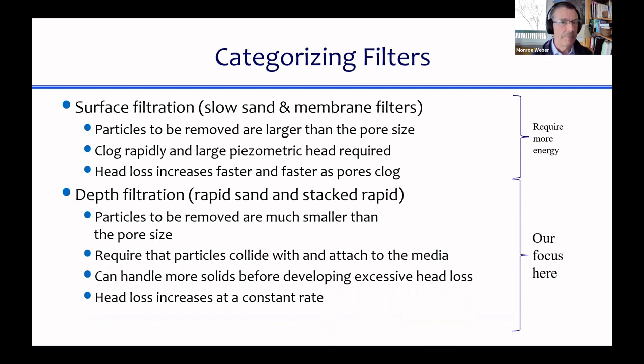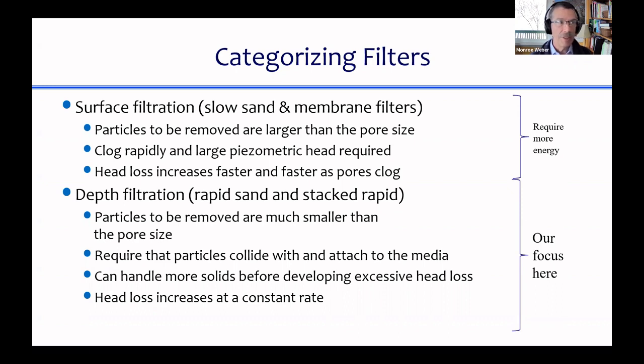You might be wondering why we don't all switch to membranes, since they sound like an awesome filter. The reason is they're still fairly expensive, they don't have a very long life, and they require lots of chemicals to keep them clean. They can't just be cleaned with backwash like sand filters. Cleaning them requires an array of chemicals, so it's messy.